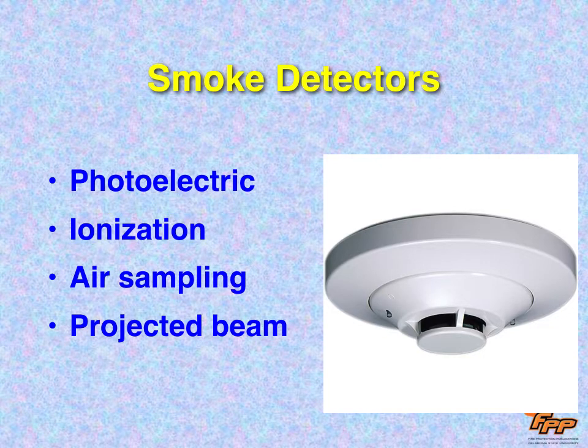Most common device is smoke detectors. They're not as fast, but they're still really fast. Within 30 seconds, it's going to detect a building fire. And if you notice, the smoke detectors have a larger hole. That's one of the ways to tell if something is a heat detector or a smoke detector. Smoke detectors need some passing of air to sample the particulates in the air. That's what they're going to sense. And so there's photoelectric, ionization, air sampling, and projected beam that you will see with smoke systems, where there's laser beams, and when particles are floating in the air, they break that laser beam, and it will sense that and set off the alarm.